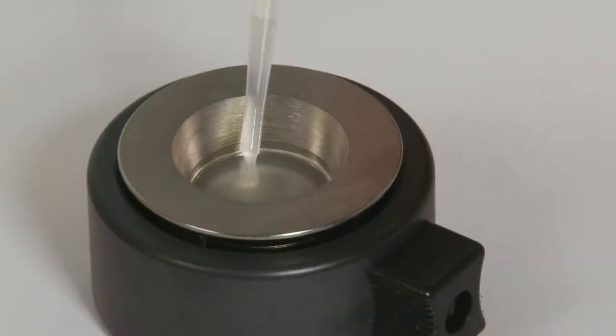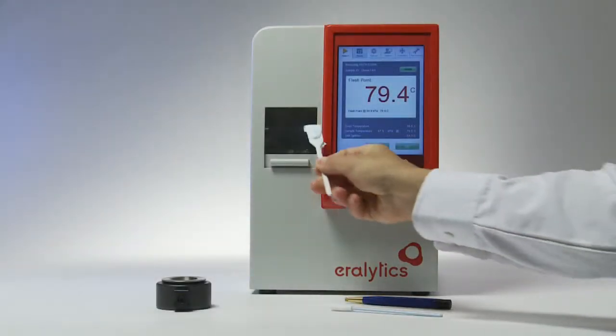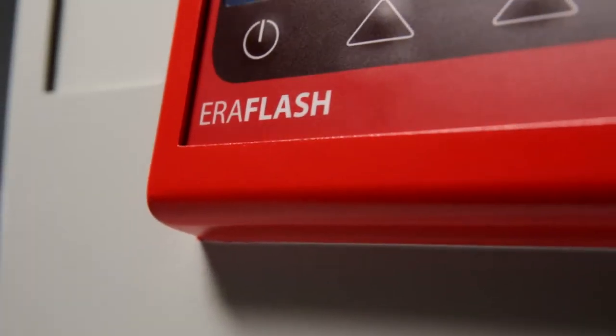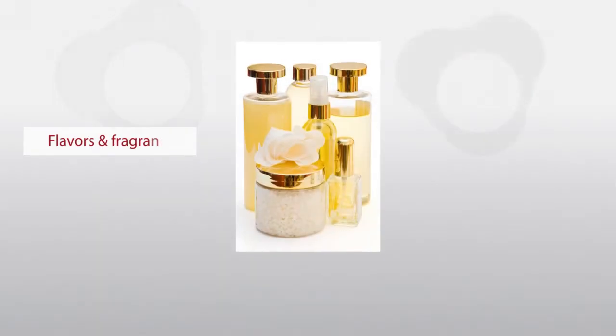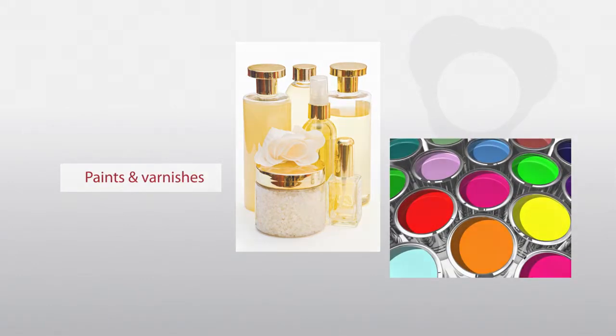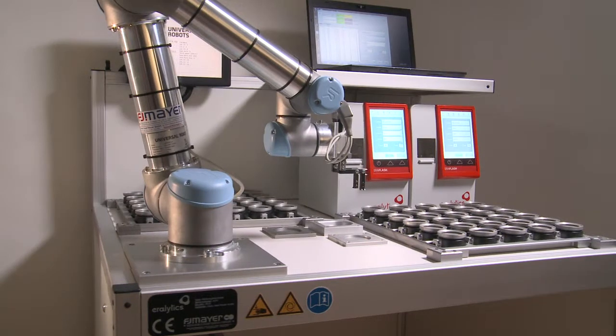The small required sample quantity of only one to two milliliters allows for economical use of expensive test substances, intelligent waste disposal, and easy cleaning of the analyzer. This makes Eraflash the preferred flashpoint tester also in the flavors and fragrances and the paints and varnishes industries.